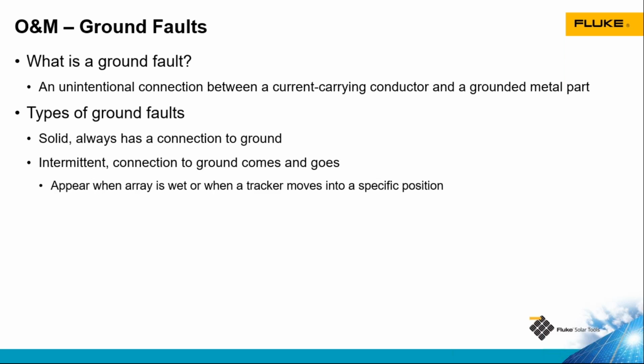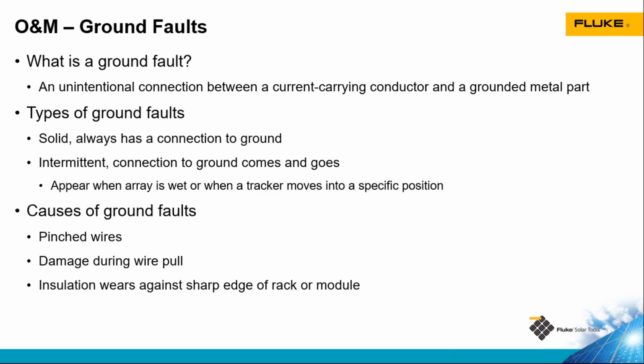They come and go. Could be a wire that's pinched by a racking, say a tracking array, and it gets pinched at a certain time of day. It could be just a high resistance connection that becomes low resistance when the array is wet. That's fairly common. Ground faults are most frequently caused by poor installation techniques. Someone, say, pinched a wire between the module and the racking when they put the module in, or they affixed the wire over the edge of a rack that was relatively sharp, and over time the wire rubbed against the racking and wore away the insulation, and now you have a ground fault.